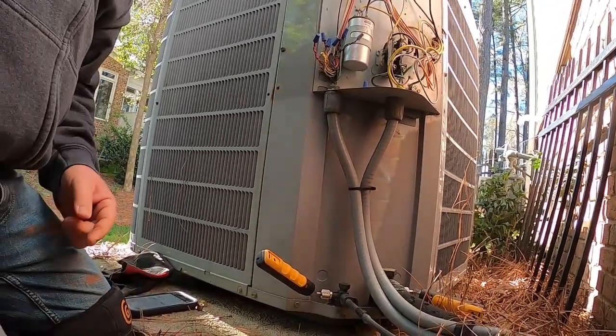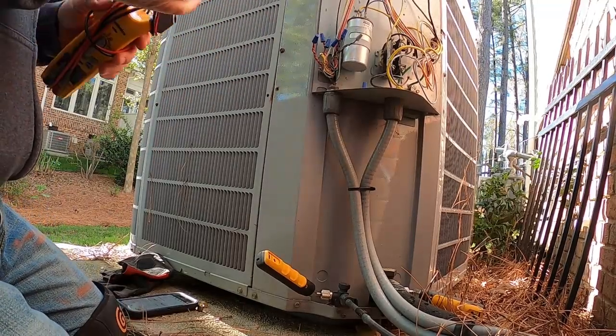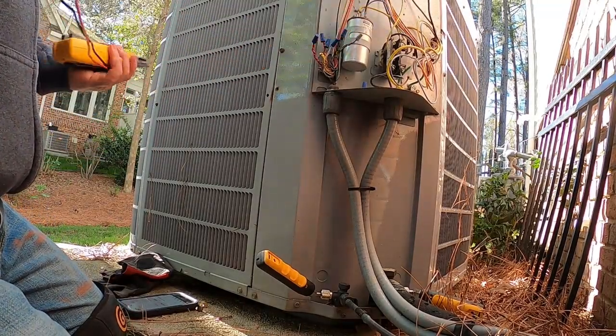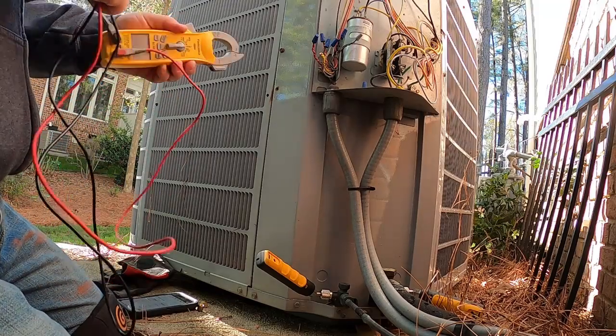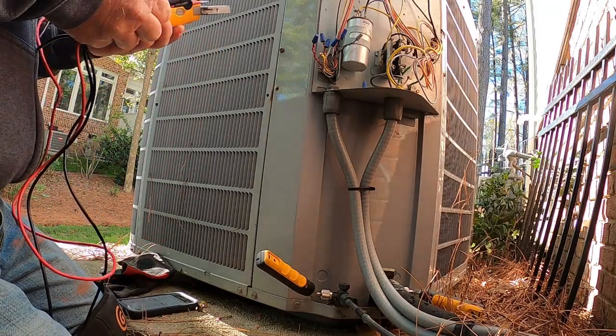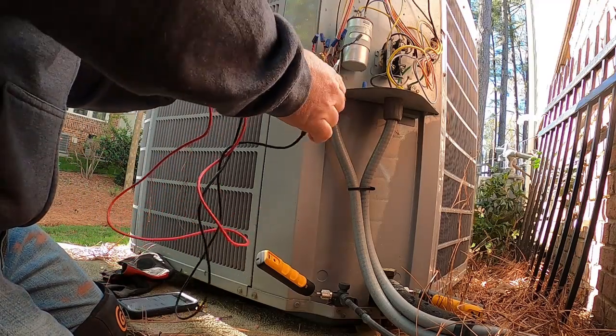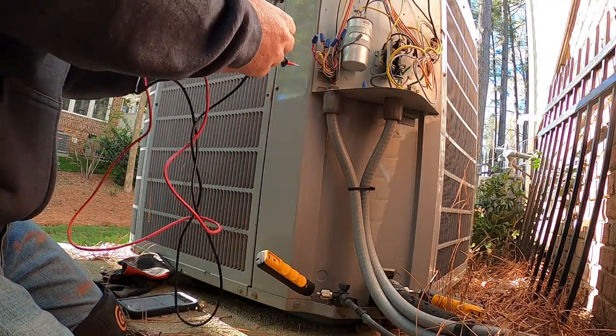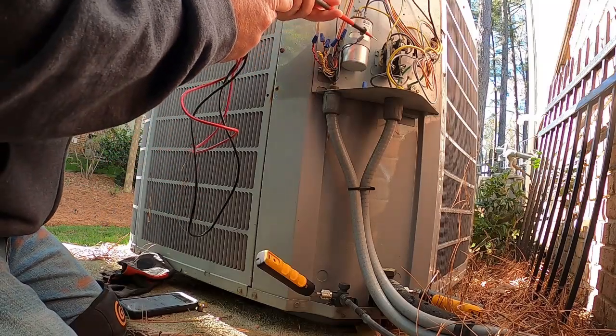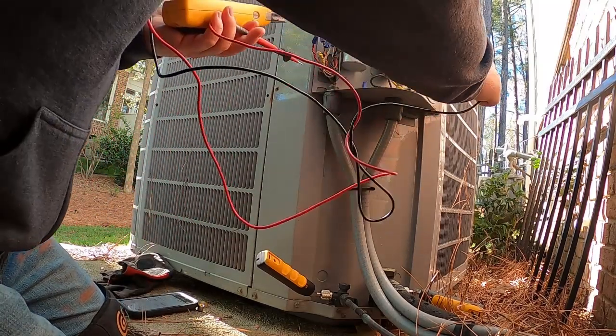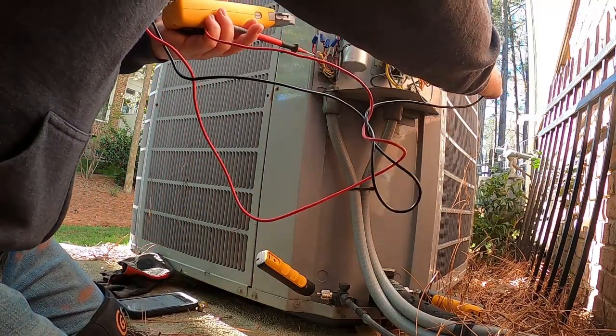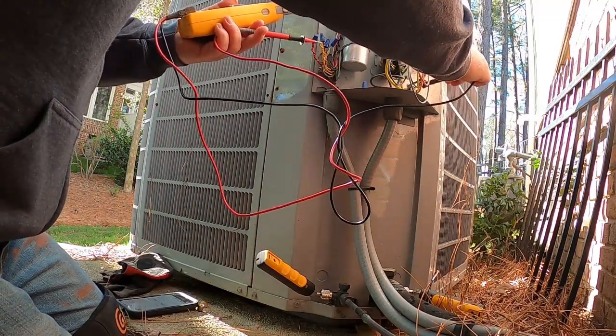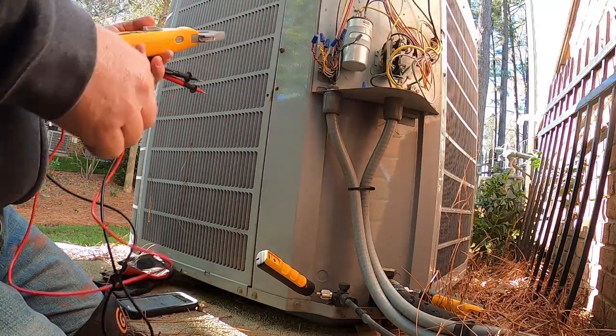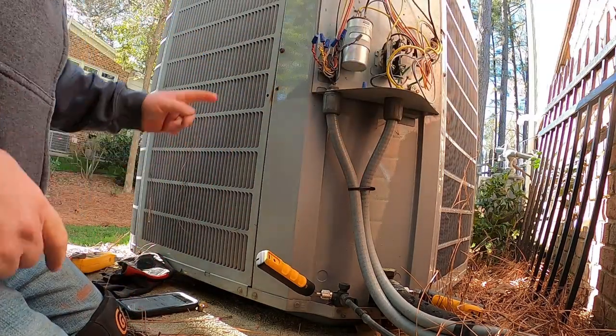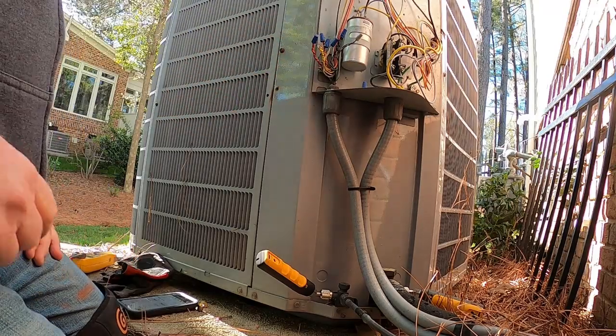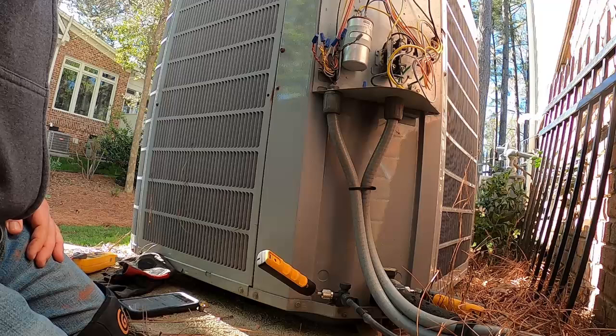If the pressures are stabilizing up now, when I got the probe turned on, it was showing me 80 psi and coming up, so more than likely it has tripped our low pressure switch. Here's my common. Here to the ground. Yep, so I do have 26 volts on my Y here. So this thing has tripped the pressure switch. I'm just going to push the contactor in.